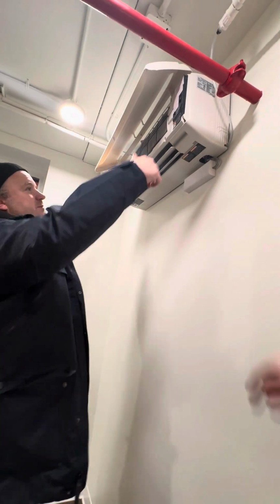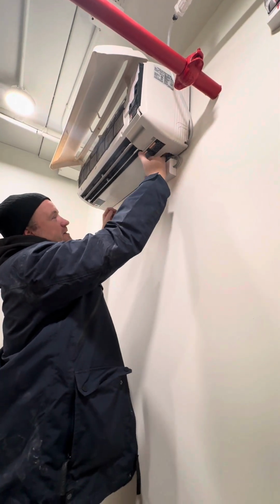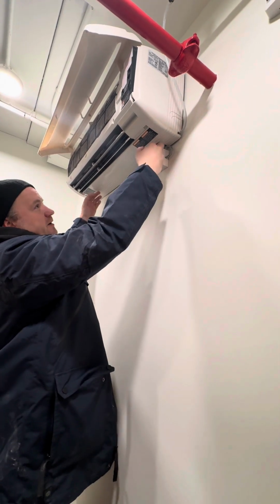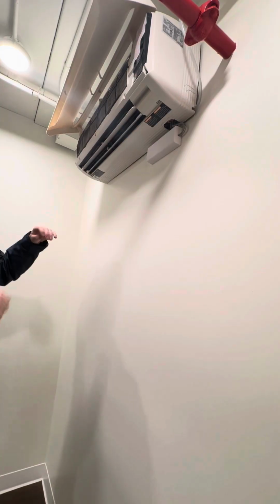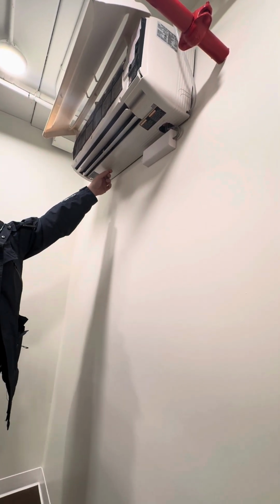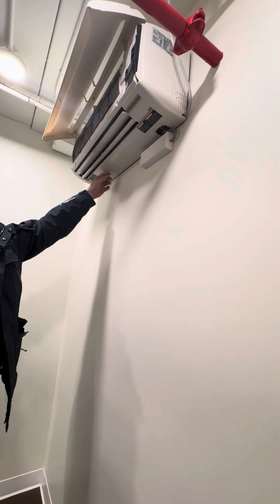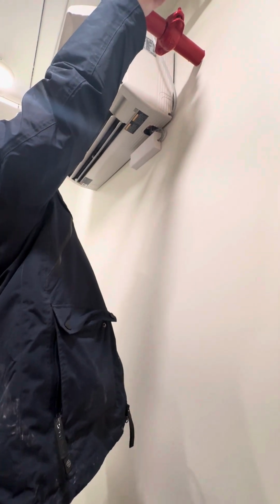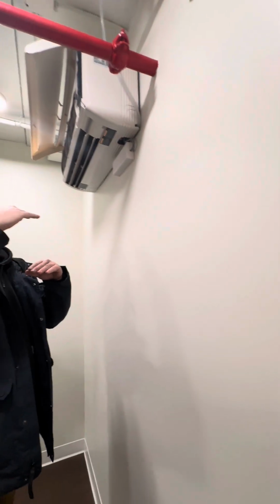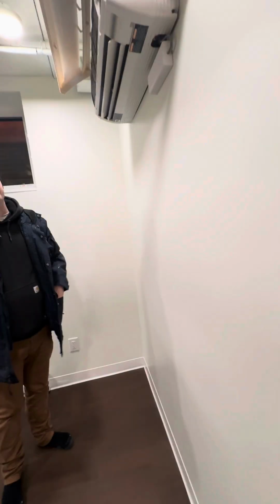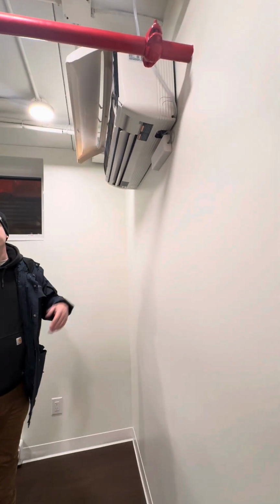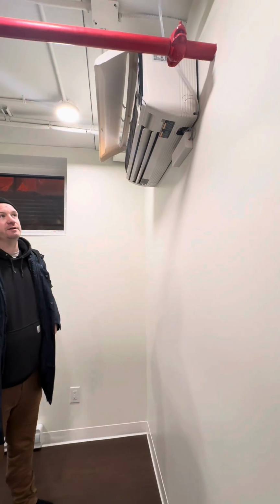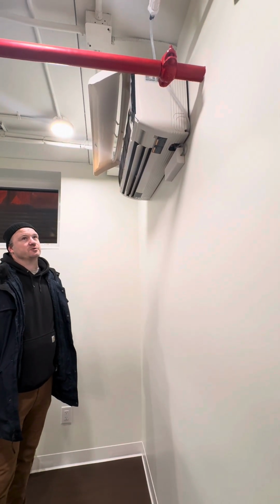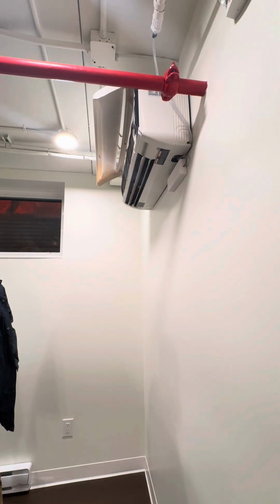There's a few screws in the front. It should just kind of pop out, and then you should be able to get access to your refrigerant lines and stuff that run in here. The pump is sitting just in there. So the water drains from the drain pan. It comes into a float. As soon as that float level rises, the pump starts, it pushes the water out. So if you've got a blockage here or in the tube or something like that, then your float level will rise to a point where it gives you a float alarm, and then it'll shut the unit down. So then you'll know, hey, I gotta take a look at my condensate pump, see if my pump's working or if the float is stuck or something. Those are really the only couple of things that you would need to look at maintenance-wise on the units.